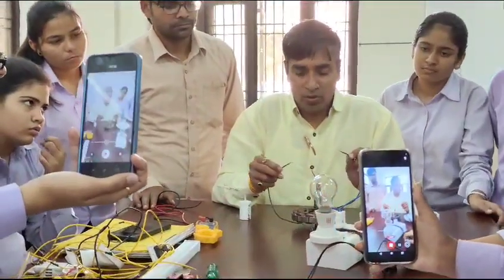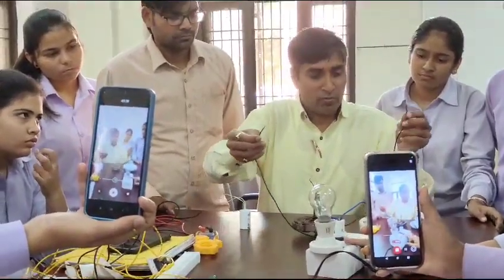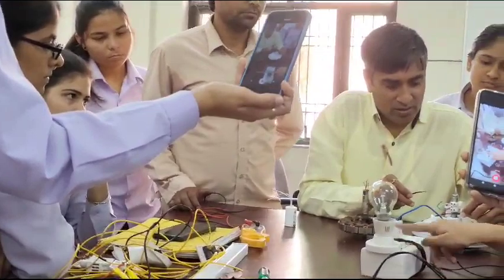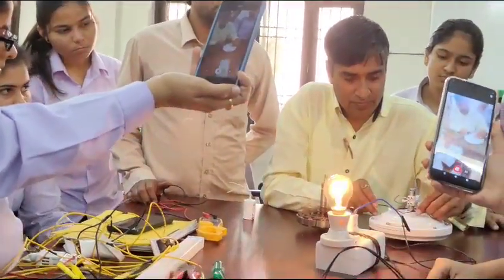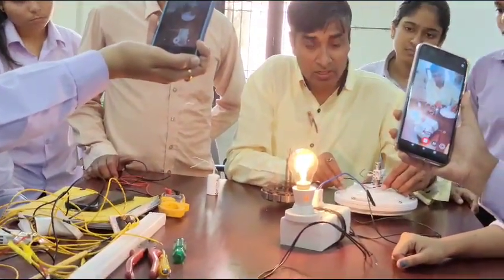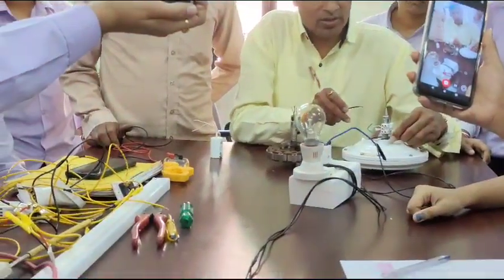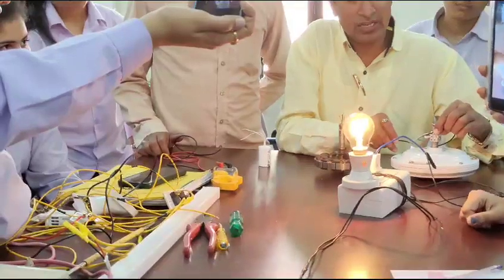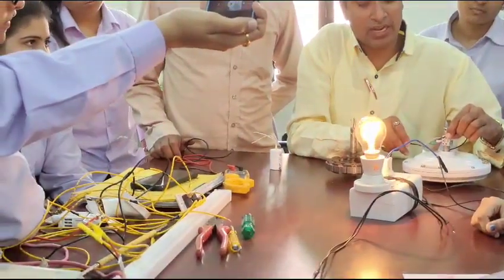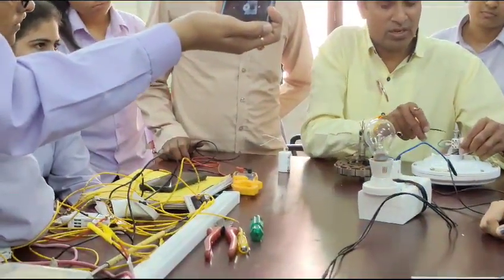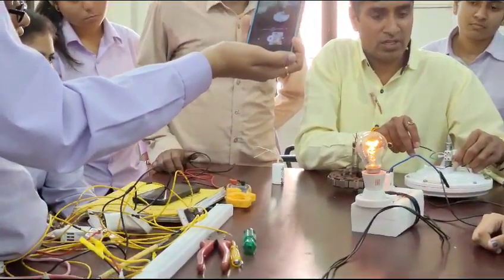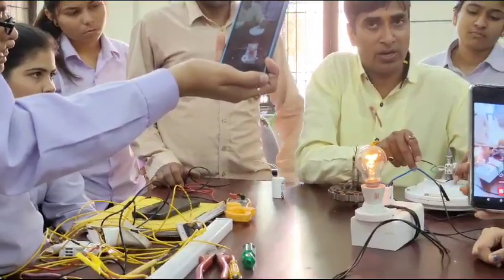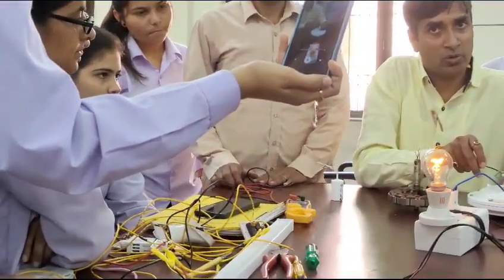Okay. Now the same thing you can see from this fan. Check, the intensity is very good. Then you see this one, the intensity is less than the previous case, so it is the starting winding. Now see this and this case, the intensity is very less, so we have to add our capacitor between the running and starting winding. Is it okay?